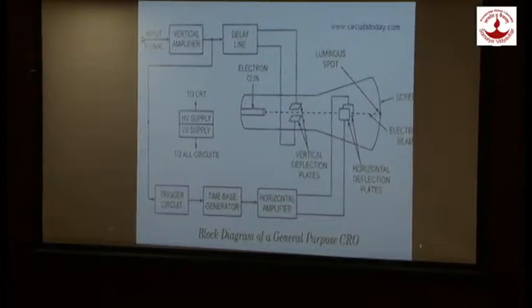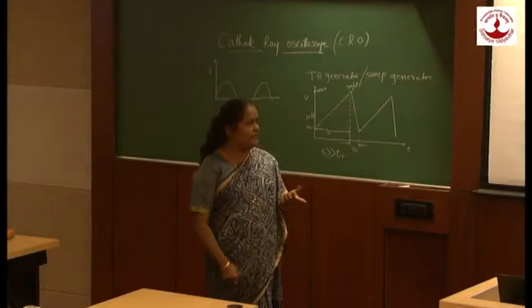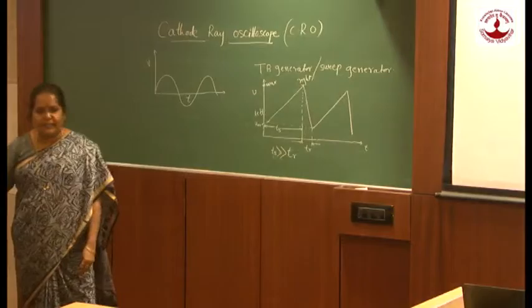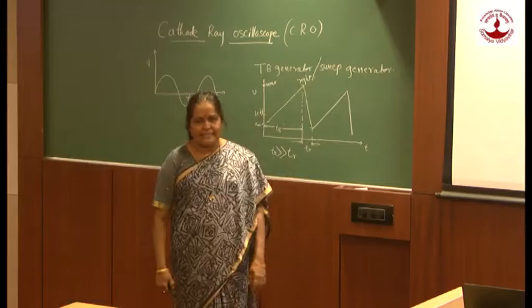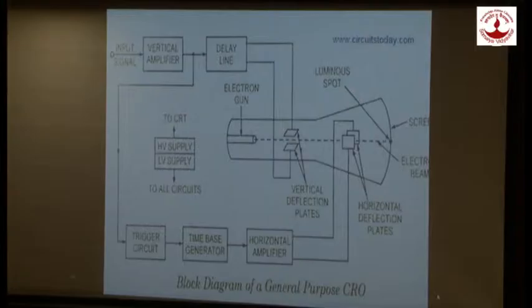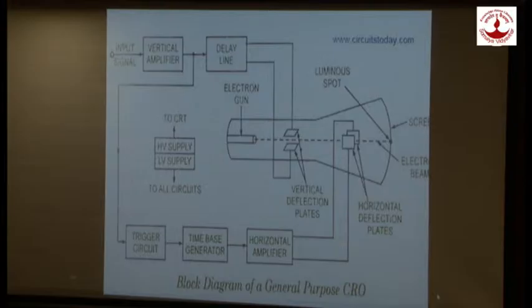The next circuit is the horizontal amplifier. Similar to the vertical amplifier, the horizontal amplifier acts as an amplifier whose gain can be adjusted by an external control on the CRO front panel — the time per division knob. It also consists of a phase inverter and push-pull amplifier circuits which give two output signals applied to the two horizontal deflecting plates. Both the vertical and horizontal signals are totally independent of each other, so the CRO spot can be traced anywhere on the screen.